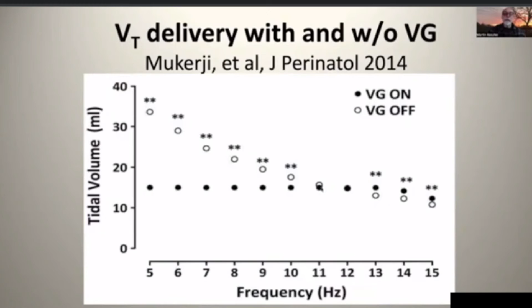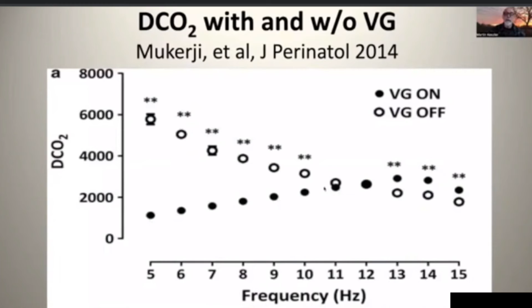You have to remember that changes in frequency will not change your tidal volume. And therefore, frequency has the usual effect on CO2 elimination, namely increasing frequency increases CO2 elimination, just like with conventional ventilation. Unlike without volume guarantee, where the effect of frequency on tidal volume overrides its effect on CO2 elimination, here it behaves more like conventional ventilation in terms of rate. Higher rate increases CO2 elimination. Very interesting. Well, what's the right tidal volume?